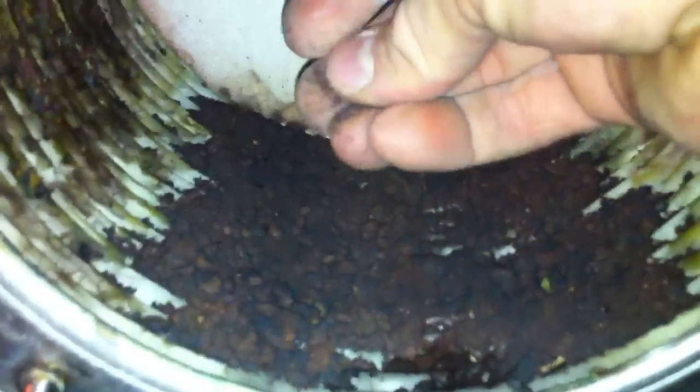You can see inside all that junk — that stuff is stopping and killing the efficiency of this appliance. Over time it all plugs up and comes out in your condensate. See how black and grimy that is? That's because all that buildup comes out with the condensate over time.